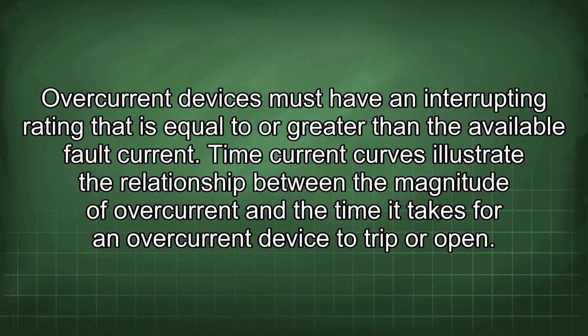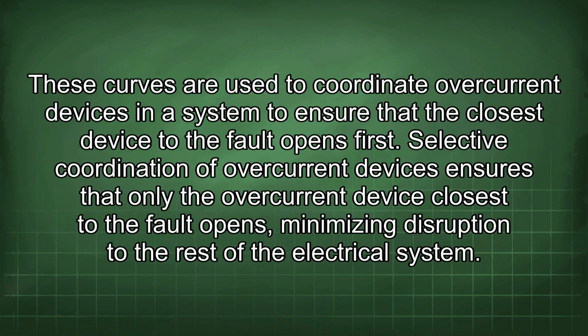Time current curves illustrate the relationship between the magnitude of overcurrent and the time it takes for an overcurrent device to trip or open. These curves are used to coordinate overcurrent devices in a system to ensure that the closest device to the fault opens first. Selective coordination of overcurrent devices ensures that only the overcurrent device closest to the fault opens, minimizing disruption to the rest of the electrical system.